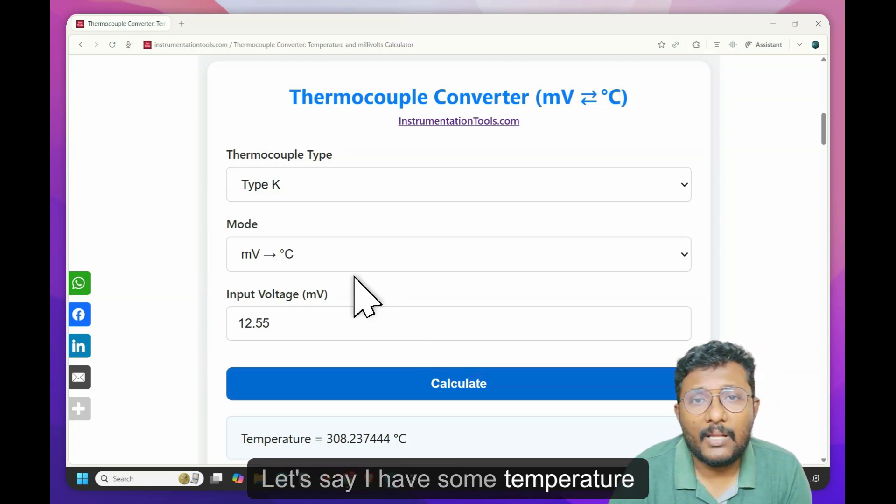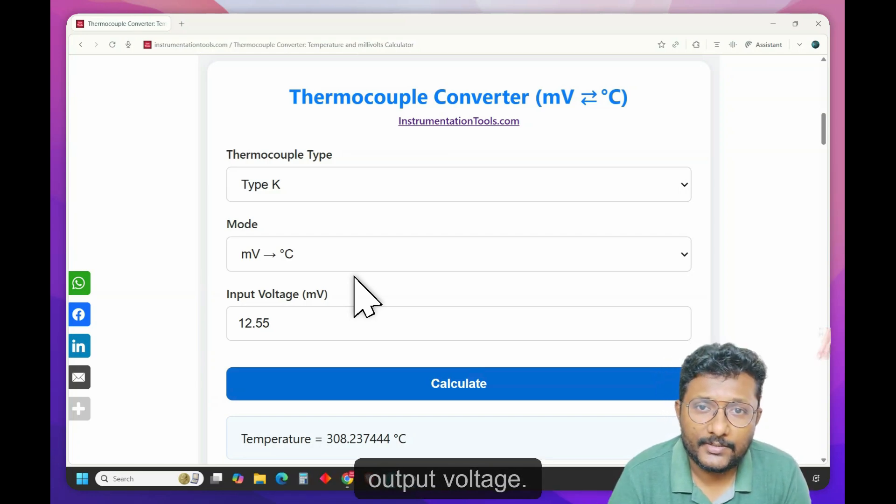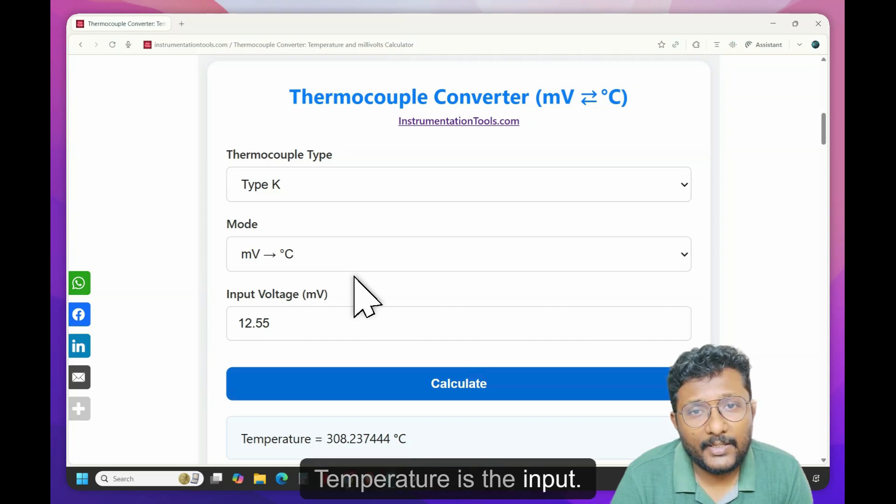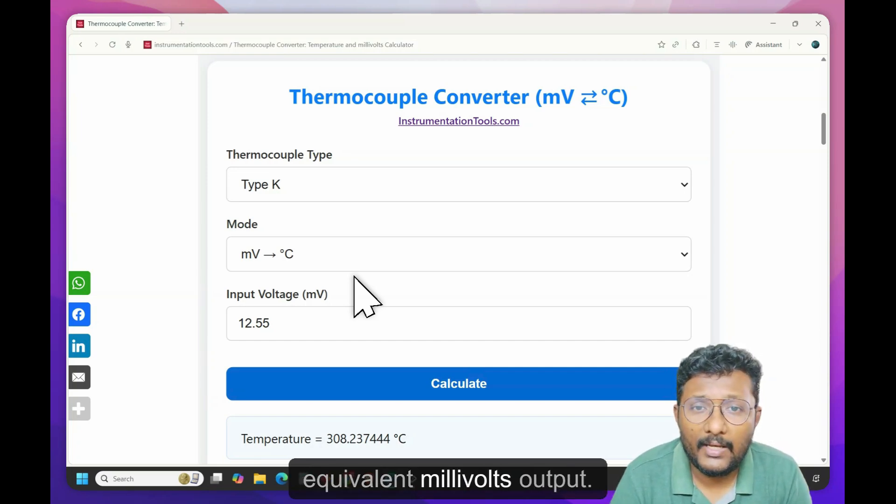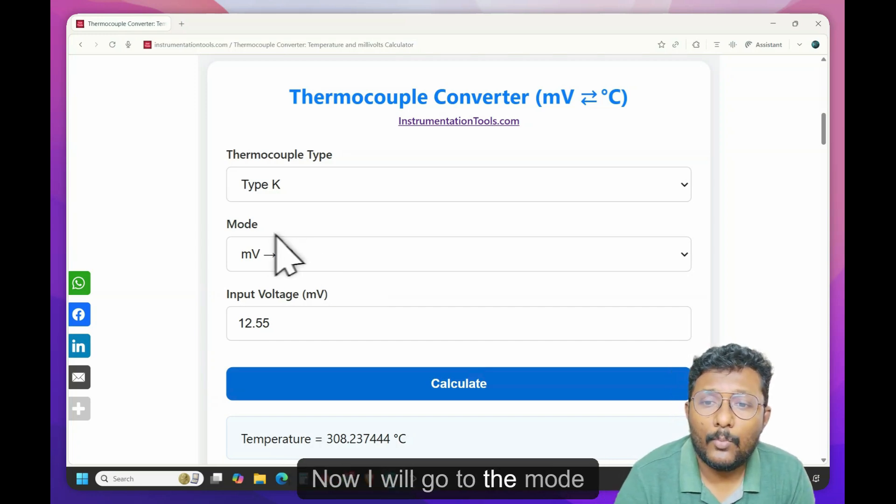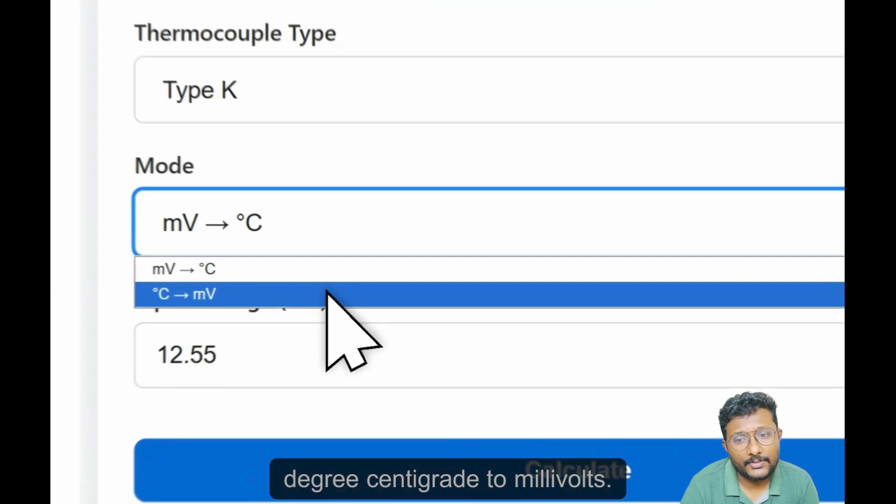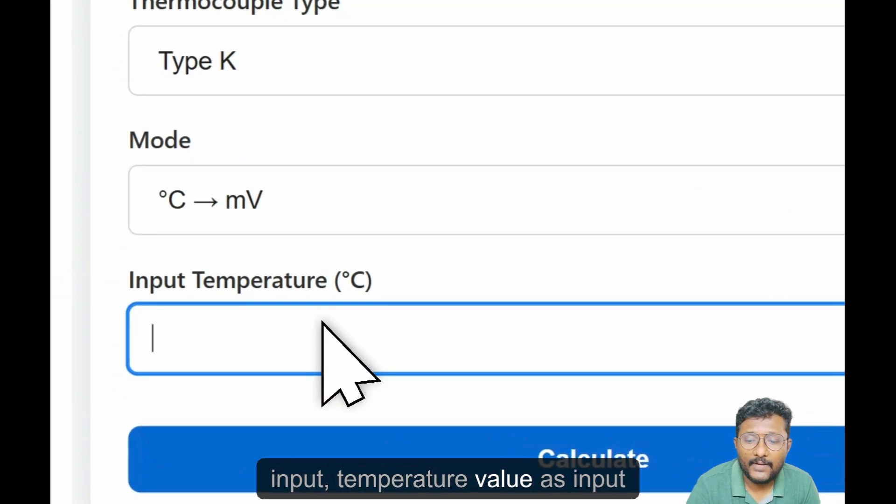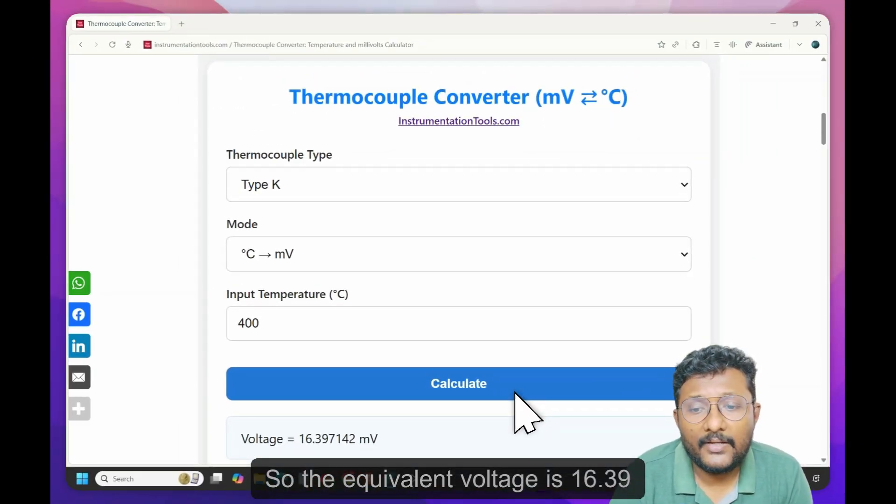Let's say I have some temperature value with me and I want to know the equivalent millivolts output voltage. So in this case, what is the input temperature is the input. Let's say the temperature is 400 degree centigrade. And now I want to know the equivalent millivolts output. Now I will go to the mode and I will select second one degree centigrade to millivolts. So here I am giving temperature input temperature value as input and then I will click on the calculate button. So the equivalent voltage is 16.39 millivolts.